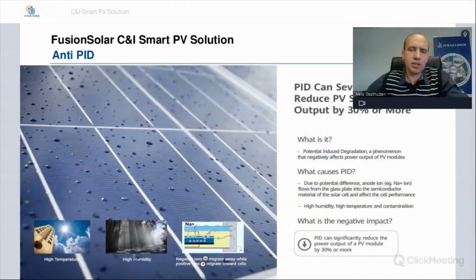The next function built into the inverters is the anti-PID, which is anti-potential induced degradation. PID can severely reduce PV system output by 30% or more. What is it? Potential induced degradation is a phenomenon that negatively affects the power output of PV modules. What causes it? Due to potential difference, anode ions flow from the glass plate into the semiconductor material of the solar cell and affect the cell performance. It is caused by high humidity, high temperature, and contamination. So PID can reduce your output by more than 50%.